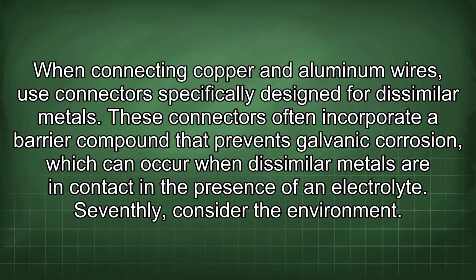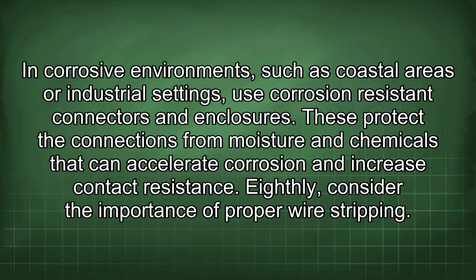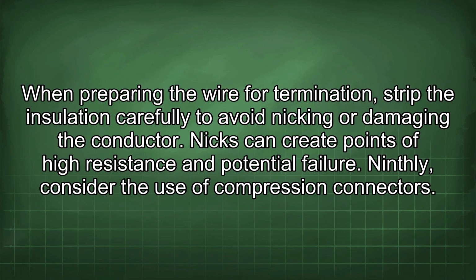Seventhly, consider the environment. In corrosive environments such as coastal areas or industrial settings, use corrosion-resistant connectors and enclosures. These protect the connections from moisture and chemicals that can accelerate corrosion and increase contact resistance. Eighthly, consider the importance of proper wire stripping. When preparing the wire for termination, strip the insulation carefully to avoid nicking or damaging the conductor. Nicks can create points of high resistance and potential failure.